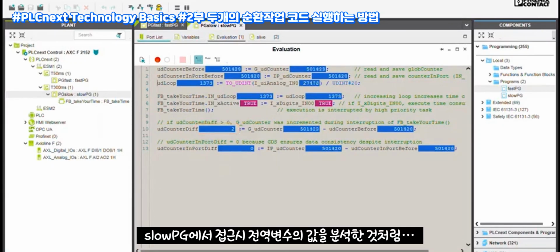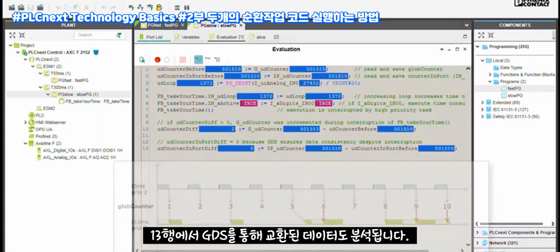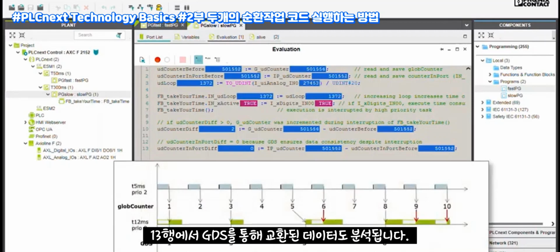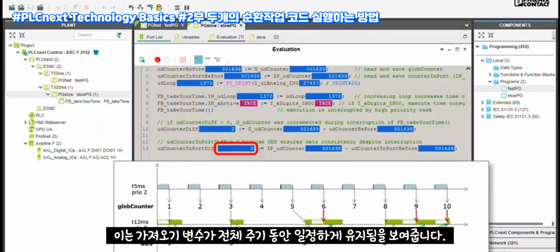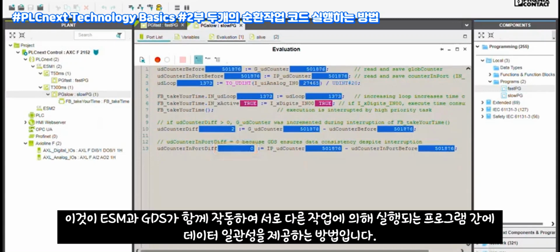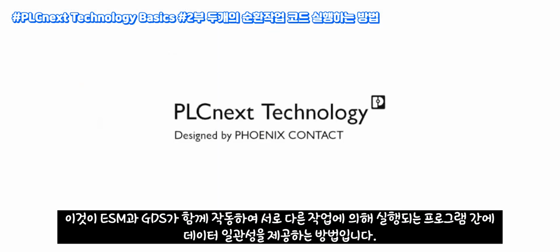Just as the value of the global variable was analyzed during access in the SlowPG, the data exchange via the GDS in line 13 is also analyzed. This shows that the import variable remains constant over the entire cycle. So that's how the ESM and the GDS work together to provide data consistency between programs that are executed by different tasks.